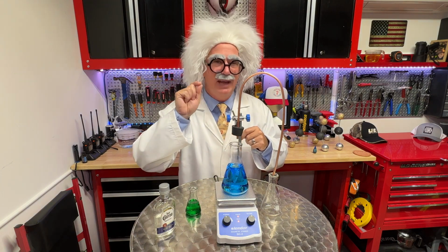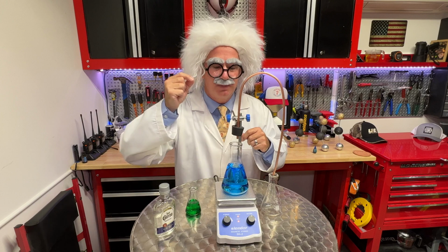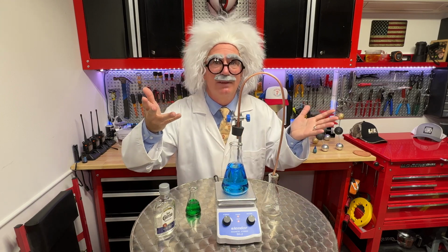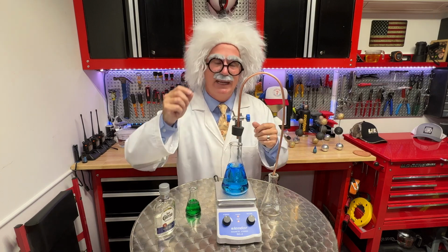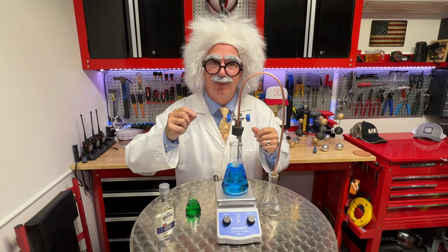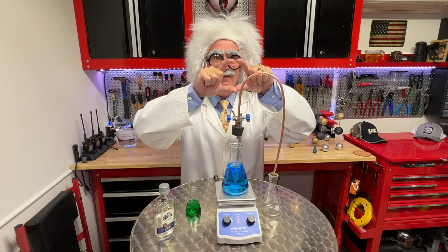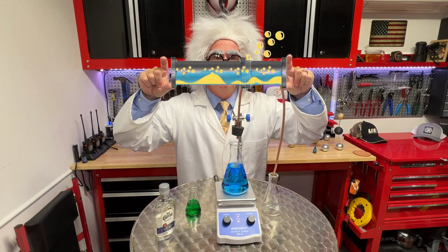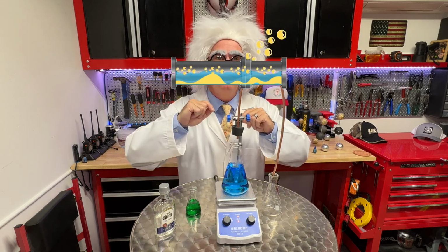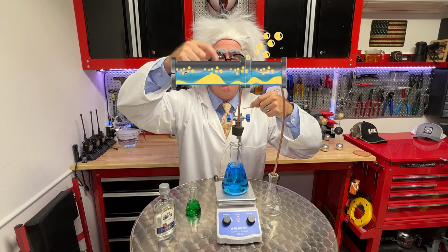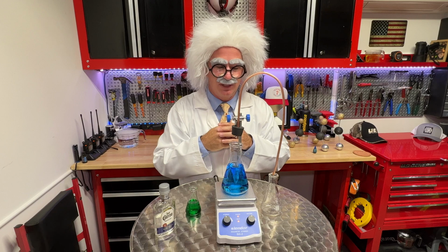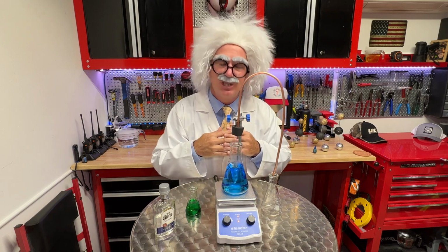Meaning that if we had a leak and it was in the right location in that point of our system, then we could actually lose one chemical in vapor form and the other would not be boiling yet. So if we were traveling on a pipe and we had liquid in the bottom and vapor at the top, but only one of our chemicals had started boiling, that means all the vapor on top is from our one chemical. And so there's the potential for fractionation.